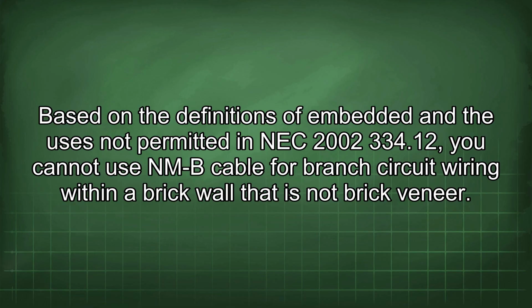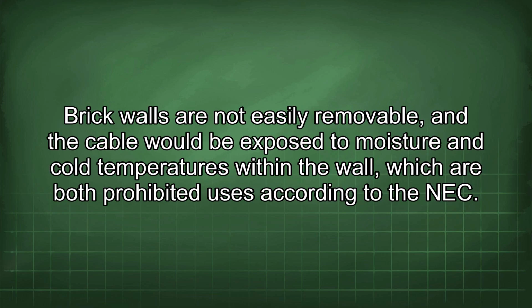2002 334.12, you cannot use an NMB cable for branch circuit wiring within a brick wall that is not brick veneer. Brick walls are not easily removable, and the cable would be exposed to moisture and cold temperatures within the wall, which are both prohibited uses according to the NEC.